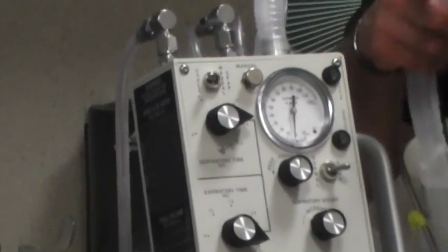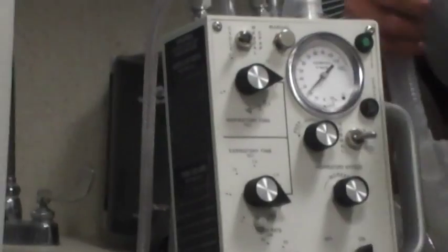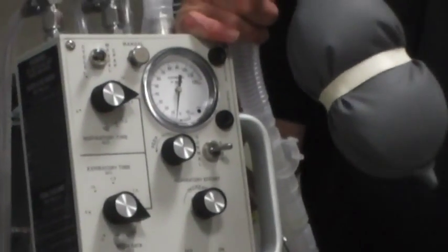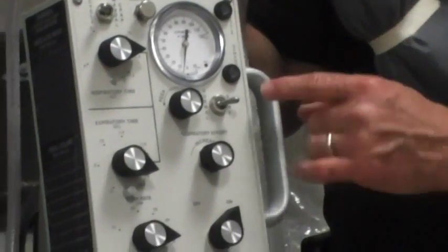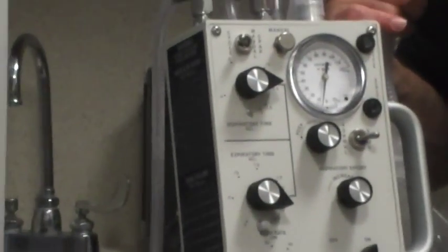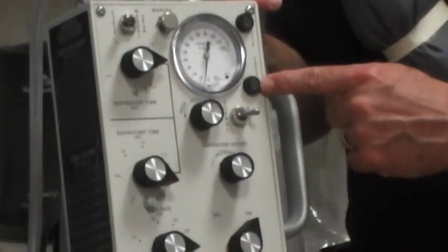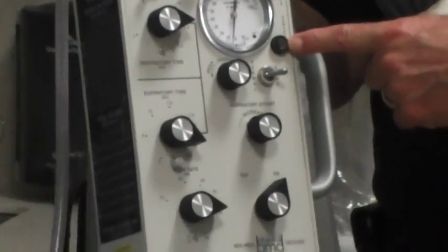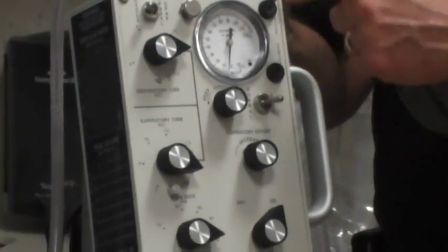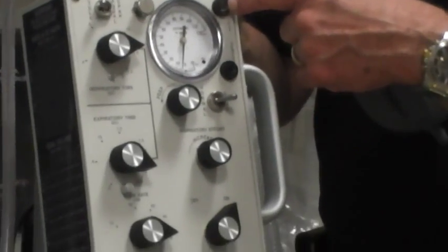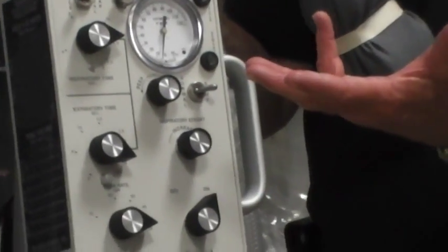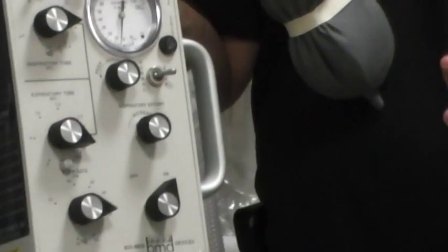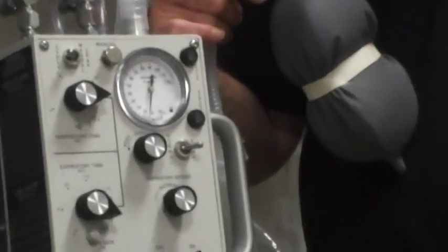Now, here's the real different part. The patient stops breathing altogether. They don't get a rate of 12. What happens is the vent has a timer. It looks for 10 seconds, and it's looking for this effort. And if it doesn't see it, after 10 seconds, it gives a breath. Well, if I was at a rate of 12, a breath every 10 seconds is a rate of 6. Probably not going to cut it.